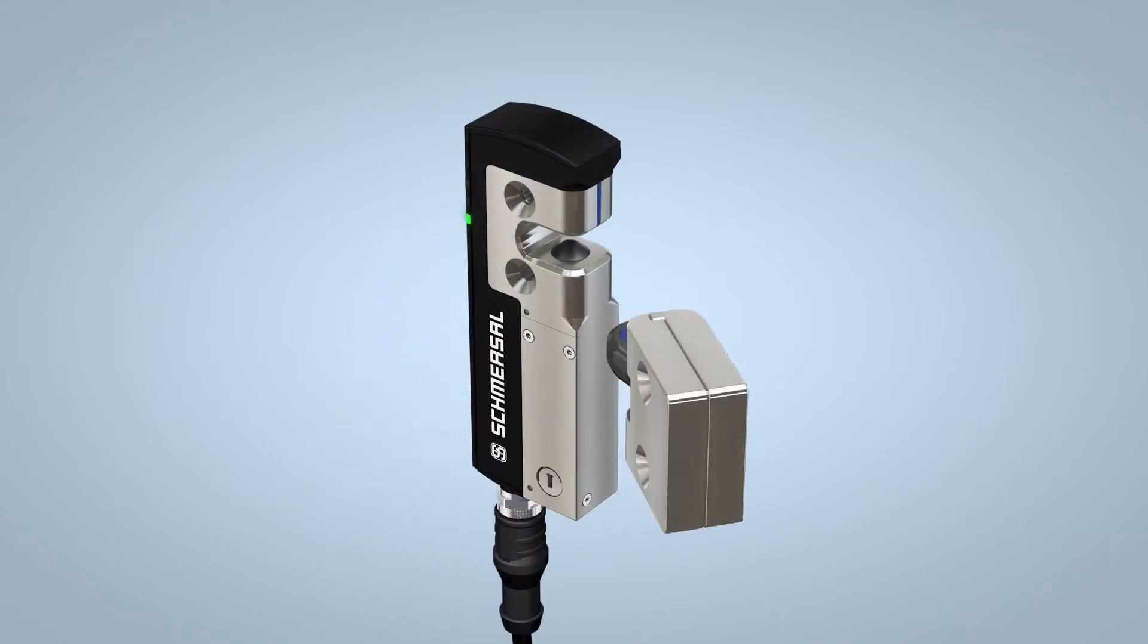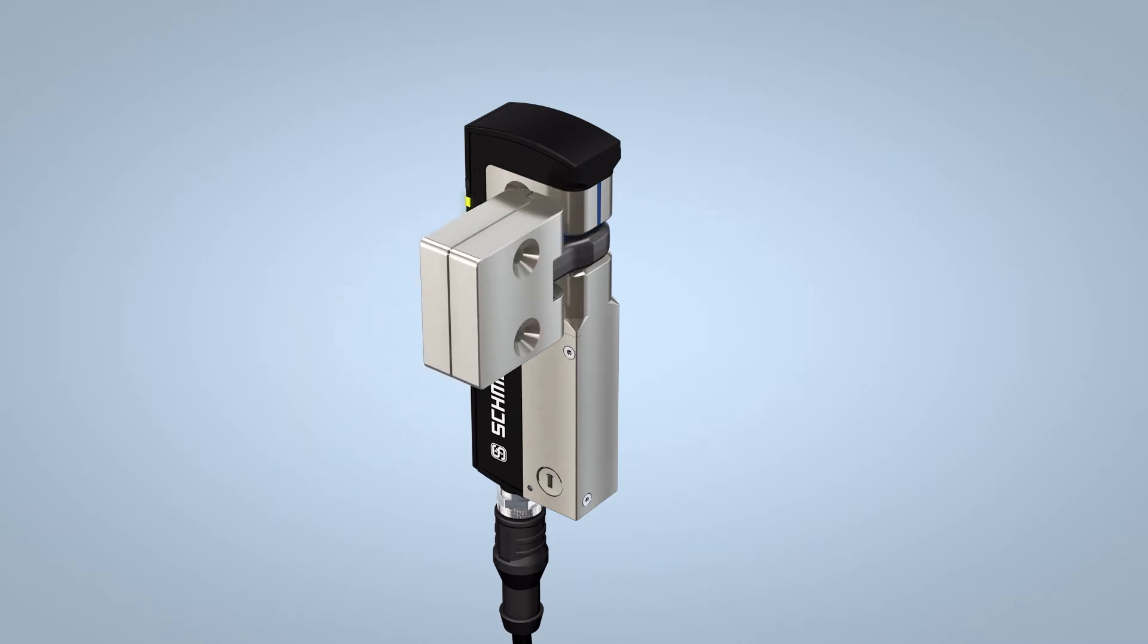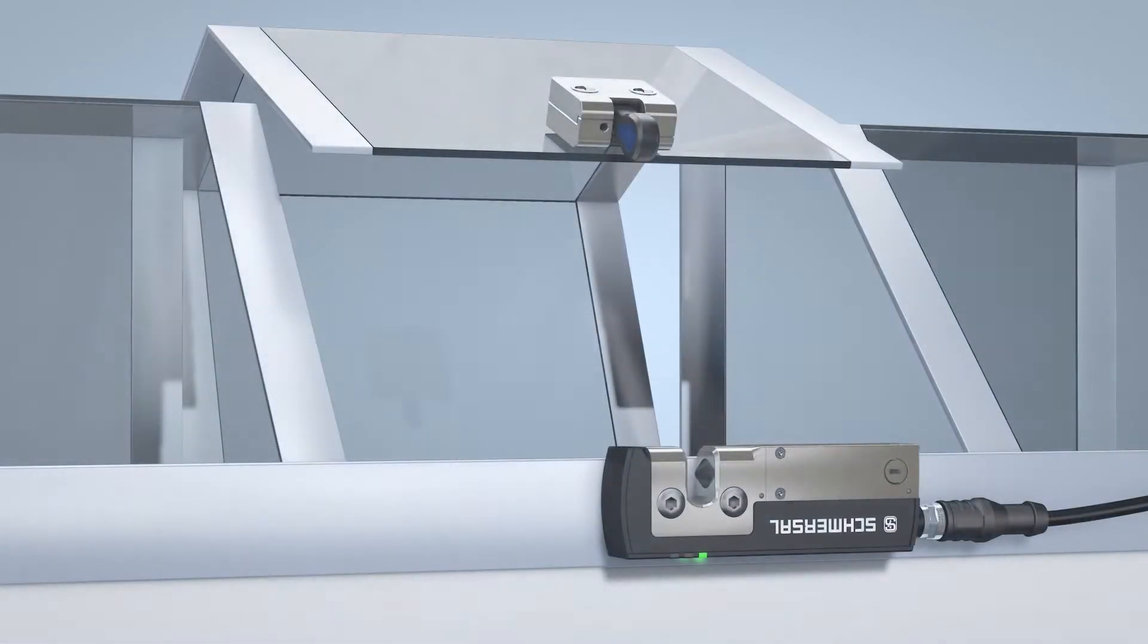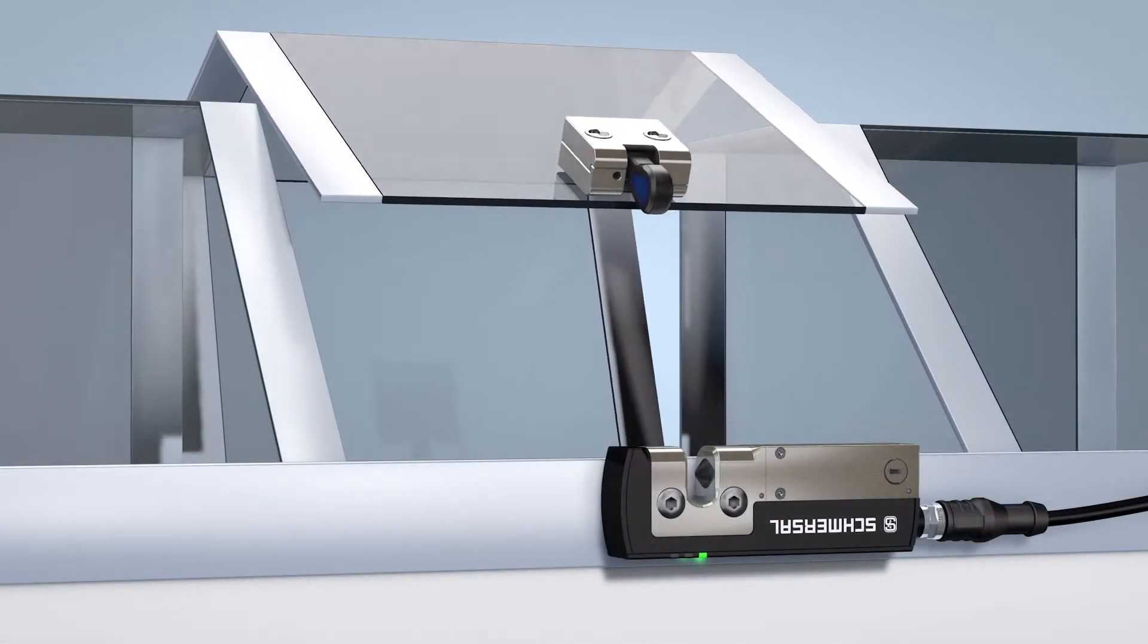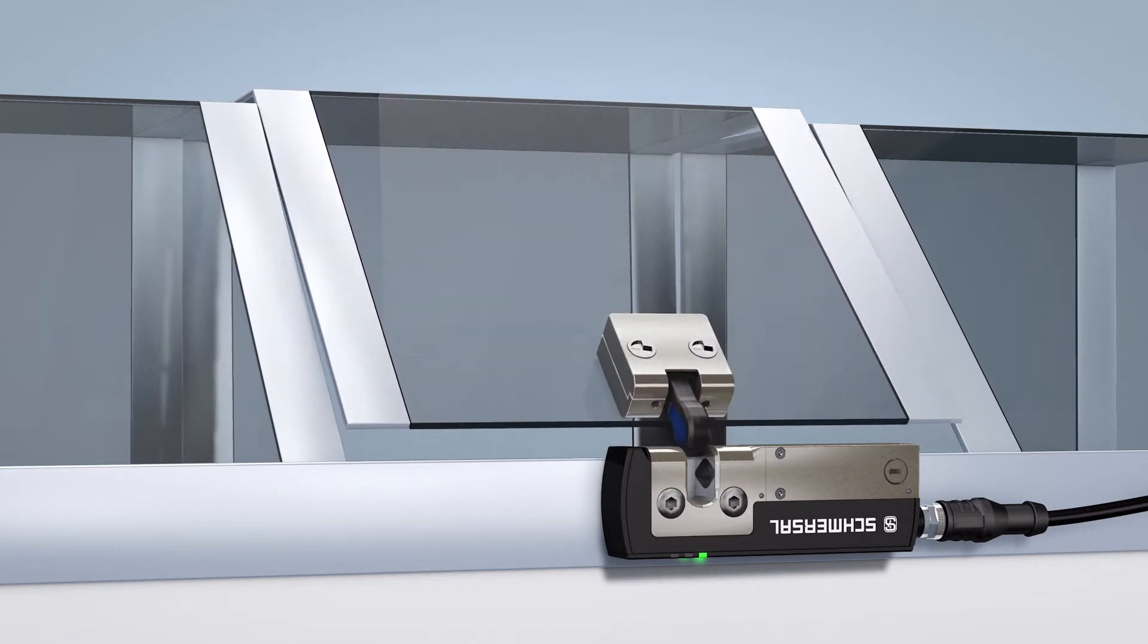As the actuator can be approached continuously within an angle of 180 degrees to the AZM40, there are additional application options. For example, the interlock can also be used on flaps that do not close in a 90 degree angle or that open upwards in a 45 degree angle.